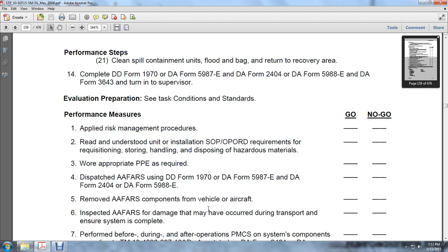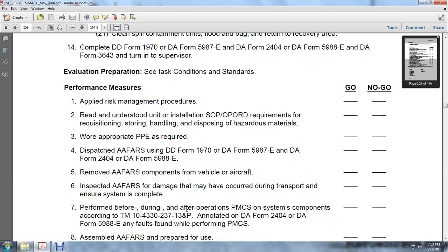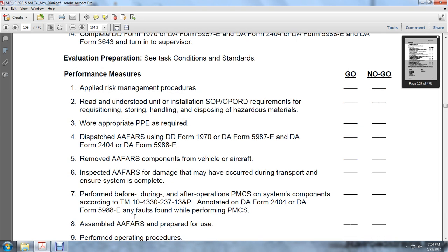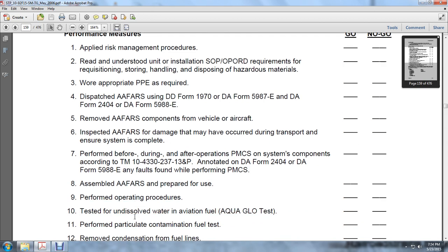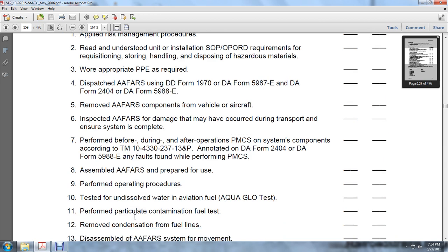Inspect the aviation forward area refueling system for damage that may have occurred during transportation. Ensure the system is complete. Perform before, during, and after operation preventive maintenance checks and services of the system per TM 10-4330-237-13P, and note on DA Form 2404 and DA Form 5988E any faults found during the preventive maintenance checks and services. Assemble the AAFARS and prepare for use. Perform the operation procedures. Test for undissolved water in the aviation fuel with the aqua-glo test. Perform the particulate contamination fuel test. Remove condensation from the fuel lines.